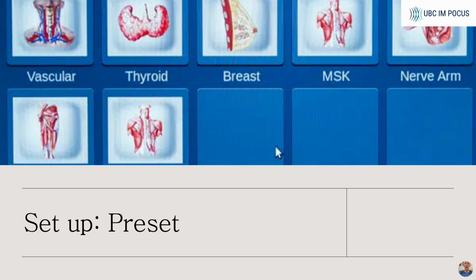available. In general, selecting the appropriate preset will provide a nice starting point for specific applications by reducing the need for additional manual adjustments. In addition, it provides access to applications, specific tools, calculators, and reporting forms. However, the right preset will not eliminate the need for fine adjustments to the image. You should still take time to optimize the image, including adjustments to gain and depth.